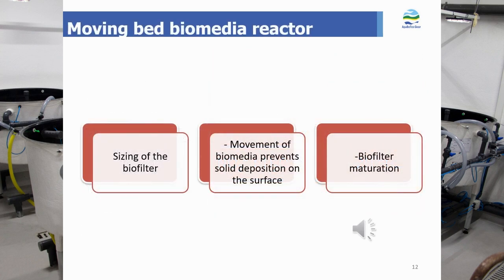One of the most common biofilter types in recirculation aquaculture is the moving bed biofilm reactor (MBBR). This is a large tank with bio-media inside, which is agitated by an air pump via an air grid creating bubbles. It is very important to size the biofilter properly; sizing depends on the total ammonia-nitrogen production per day, which in turn depends on how much fish is grown in the culture tanks.